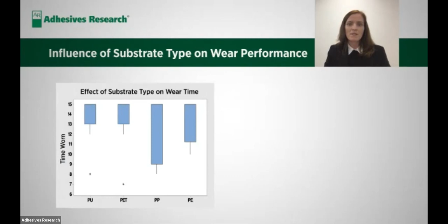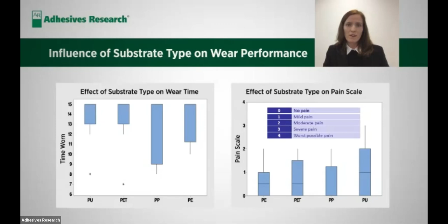In contrast, when we look at the pain scale and removal ratings, we can see that the PU and the polyester samples performed less favourably than the polypropylene and the polyethylene samples. This information can be used to select the best substrate for the application. So for instance, if a wear time of 14 days was the most critical attribute, then a polyurethane or a polyester substrate would be the most preferred candidate. But where you may have geriatric or pediatric skin, then the polyethylene substrate may be the best choice. That is why it is so critical to understand where the device is going to be worn and what target market. Adhesive selection for skin attachment is critical to assure proper therapeutic dose delivery and device function.